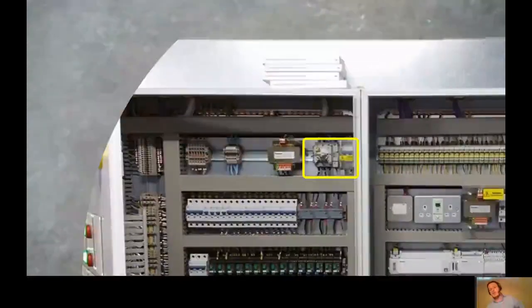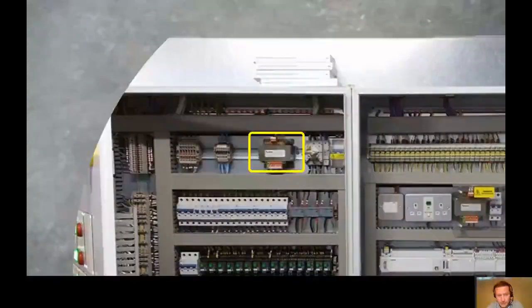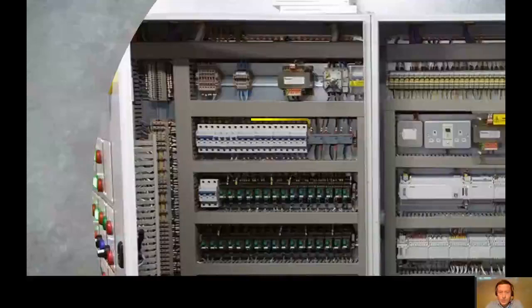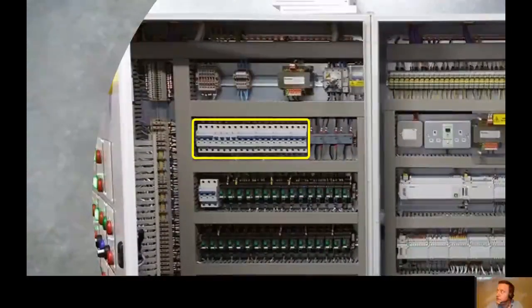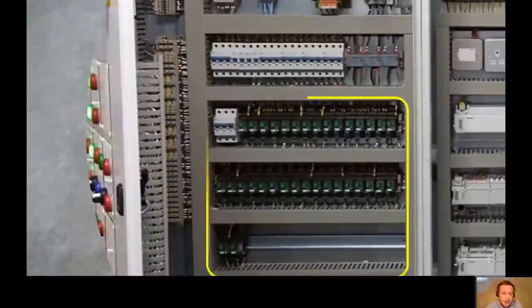Moving into the power side, we have our power input, which is where the isolator is. We'll then have our power side 24-volt transformer, which feeds the different things within the power side. We then have the main MCBs that are feeding the various plant items like motors and boilers and things like that. And then we have our control relays, which is effectively the staged switching of things like contactors, whatever needs to be switched out into the field in a staged format.